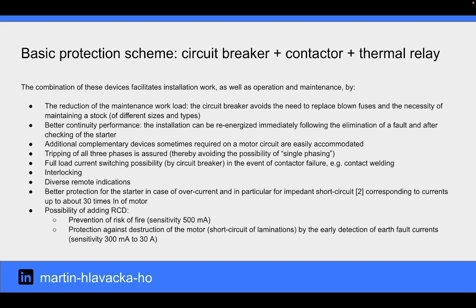Additional complementary devices sometimes required on a motor circuit are easily accommodated. Tripping of all three phases is assured. Full load current switching possibility in the event of contactor failure. Interlocking. Diverse remote indications. Better protection for the starter in case of overcurrent and in particular for impedance short circuit corresponding to currents up to about 30 times nominal current of motor. Possibility of adding RCD for prevention of risk of fire and protection against destruction of the motor by the early detection of earth fault currents.